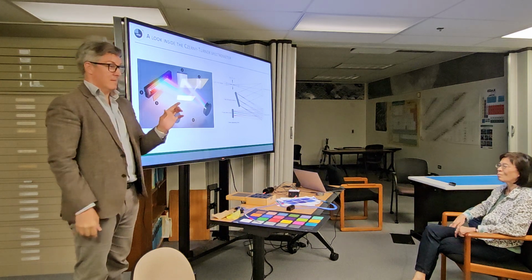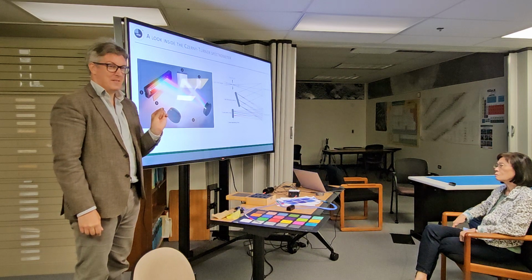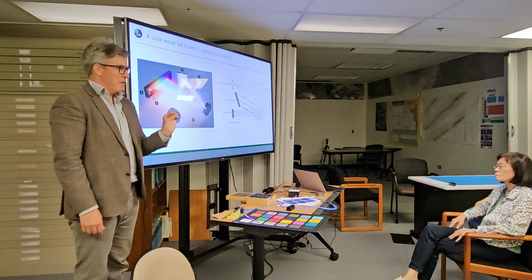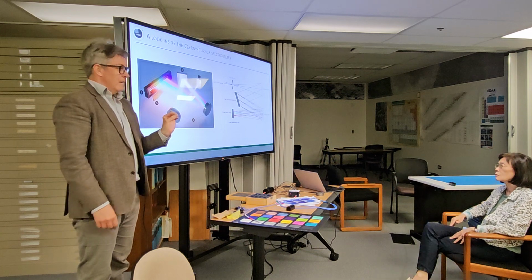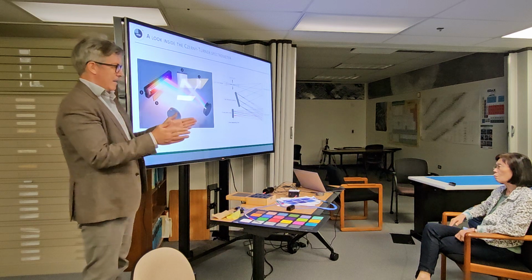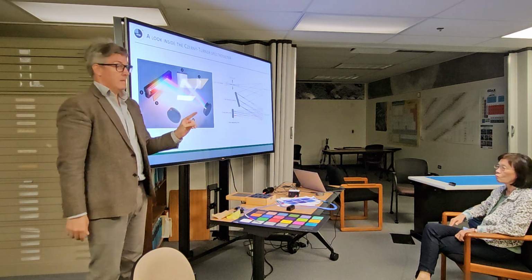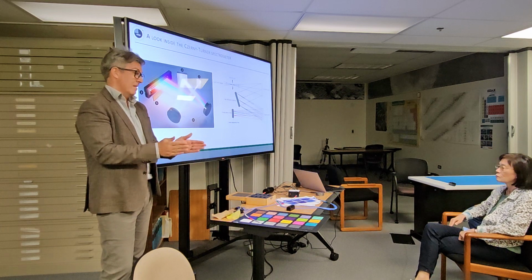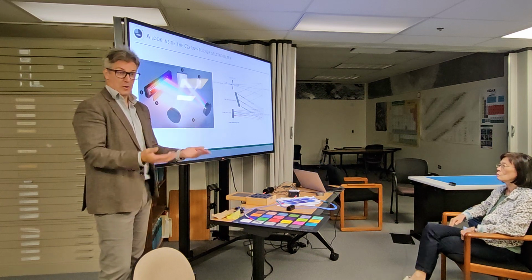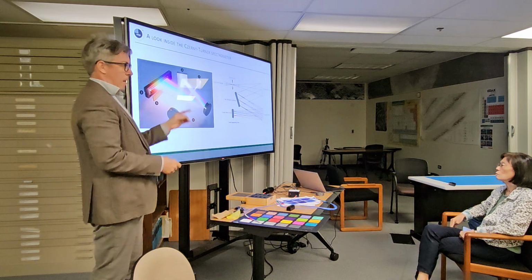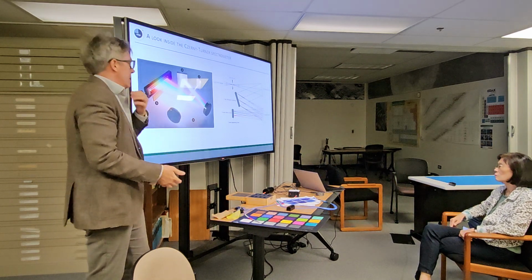How about if I make the slit nothing? How much light would enter the spectrometer? 0, right? So the narrower I make the slit, the higher the spectral resolution, and I'll describe that, I can achieve with this spectrometer. But the less light I admit, so my signal to noise goes down. The wider the slit, the more light I admit, but the worse my spectral resolving power. Right. So again, this is part of the spectrometer design process.